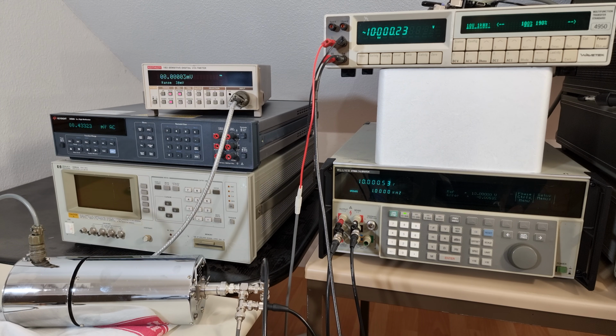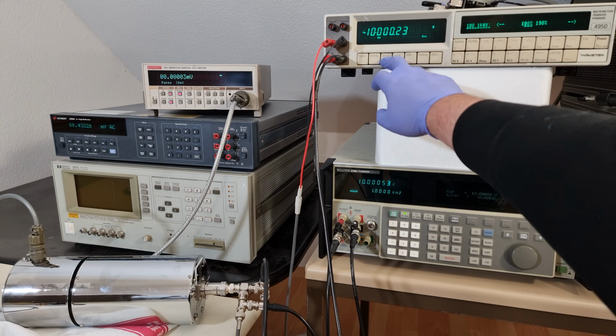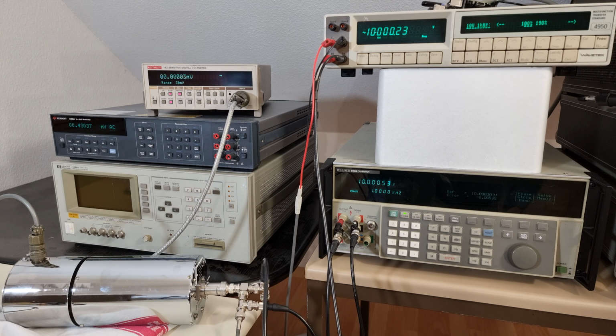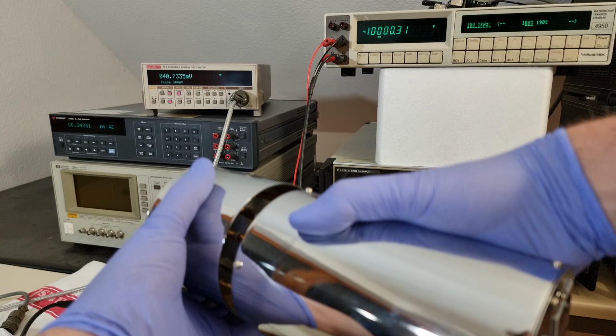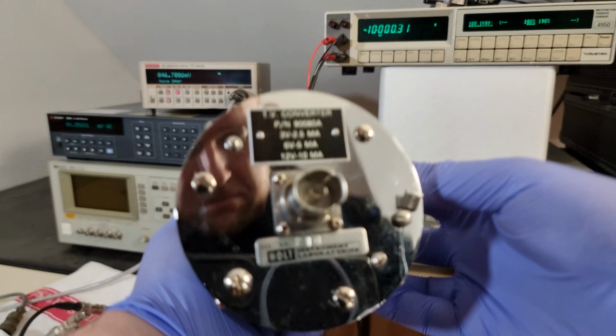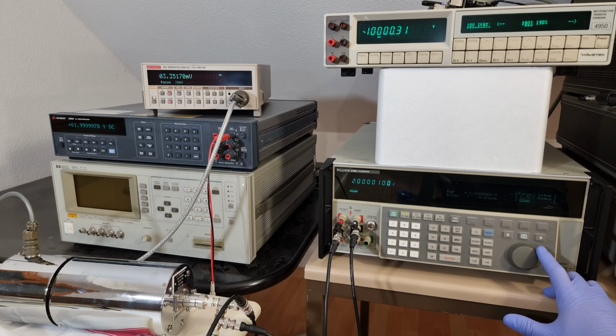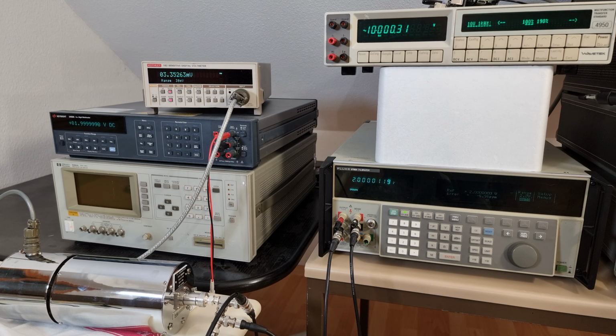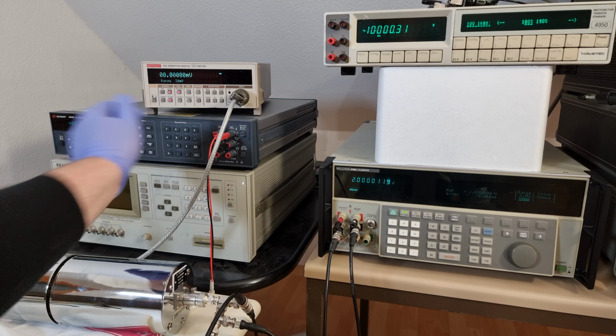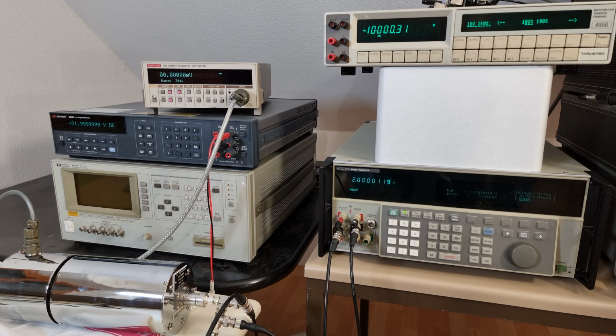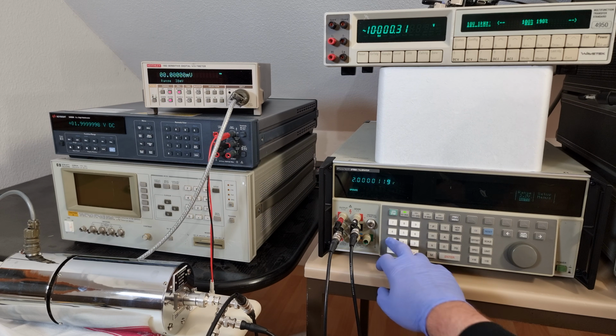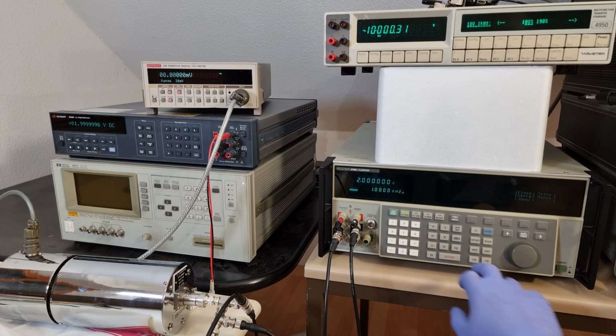Yeah, okay, this is amazingly close, because we are directly on the spot calibration point of interest. Let's try the same procedure at 2 volt. I'll build the most sensitive converter combination for 3 volt. I'll create a 2 volt DC signal based on 3458A, taking advantage of its unmatched DCV linearity. I'll zero out the nanovoltmeter when the thermal converter has stabilized. I'll feed 2 volt 1 kHz into the thermal converter and fine-tune it until the nanovoltmeter reads exactly 0 again.